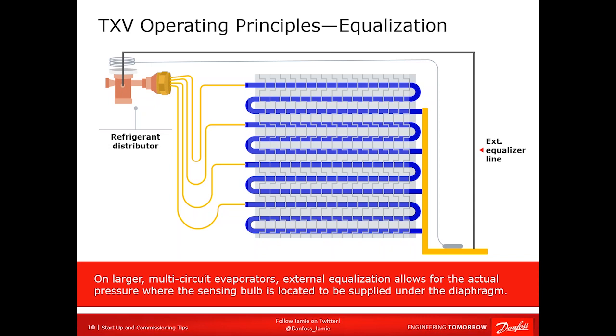So the rule is, you can use an external equalized TXV even if you really don't need it. However, you can never use an internal equalized TXV if you need an external one. And remember, even if you don't need it, you still need to connect that equalizer line. The TXV will not open without that equalizer line connected. I have seen that before. Please don't do it.